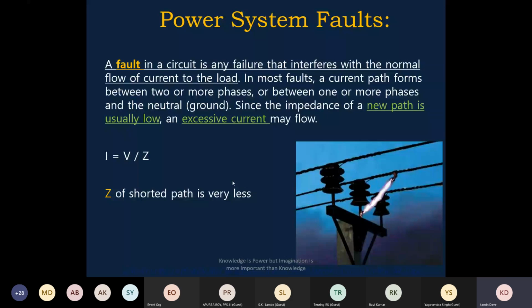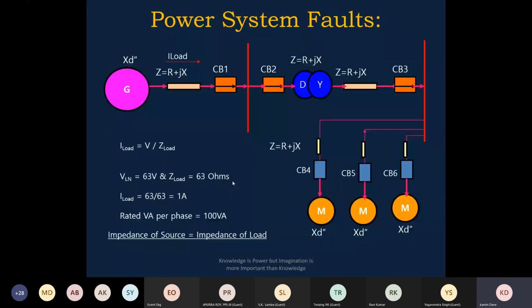So when we see the small network, that is generator, then cable, breakers, then distribution transformers or transformers, and then there is a load. So I load is equal to V divided by Z load. Suppose V LN is equal to 63 volt and Z load is equal to 63 ohms, then I load is equal to 1 ampere. What it does mean is that the rated VA per phase is equal to 100 VA. Here V LN is 63 volt, Z load is equal to 63 ohms, and I load is equal to 1 ampere. So this is within 100 VA.